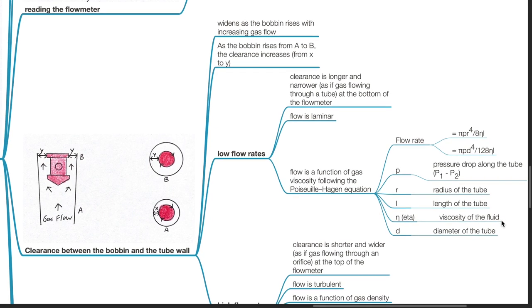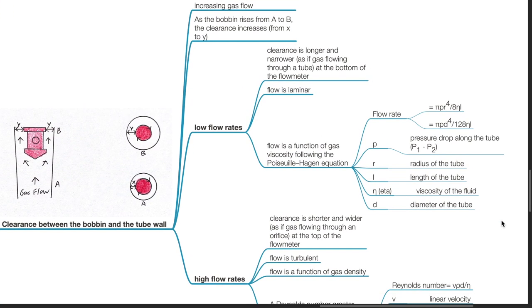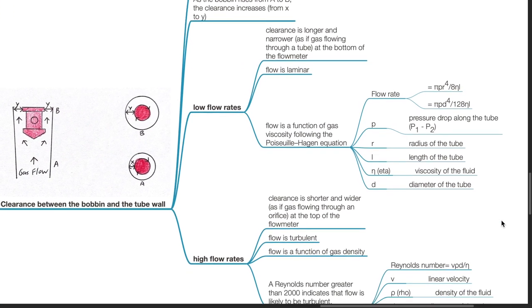At low flow rates, the clearance is longer and narrower, as if gas flowing through a tube at the bottom of the flow meter. The flow is laminar and flow is a function of gas viscosity following the Poiseuille-Hagen equation. Flow rate equals pi p r to the power of 4 divided by 8 eta l, or pi p d to the power of 4 divided by 128 eta l, where p equals pressure drop along the tube p1 minus p2.